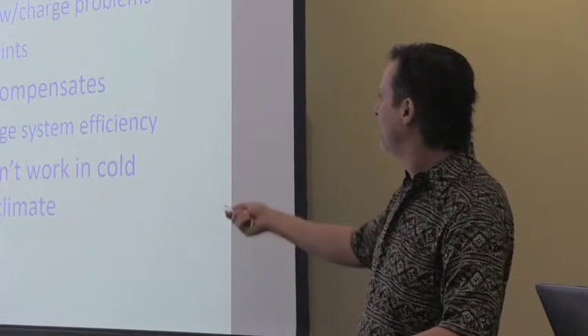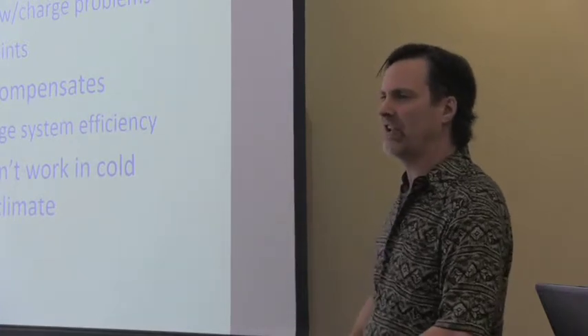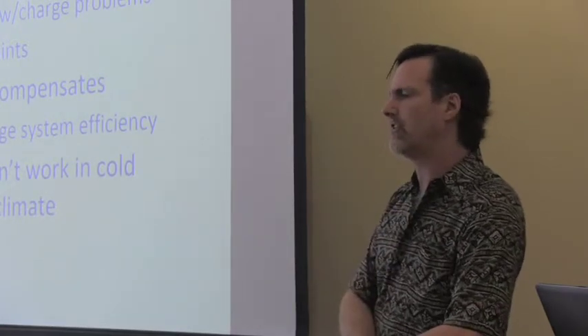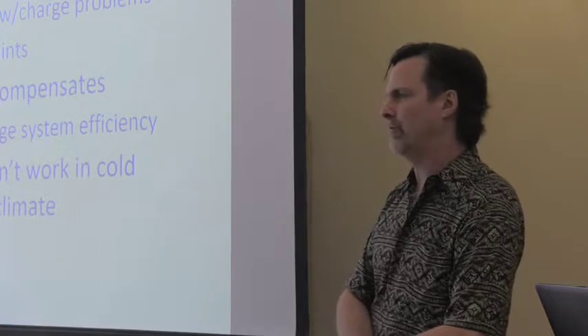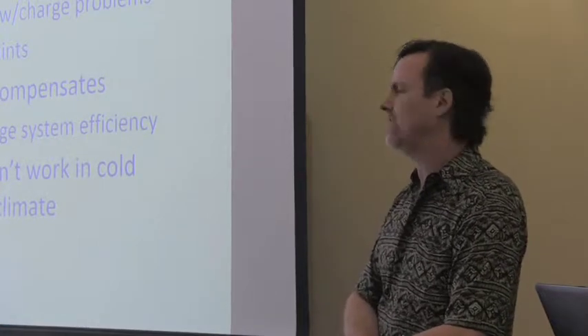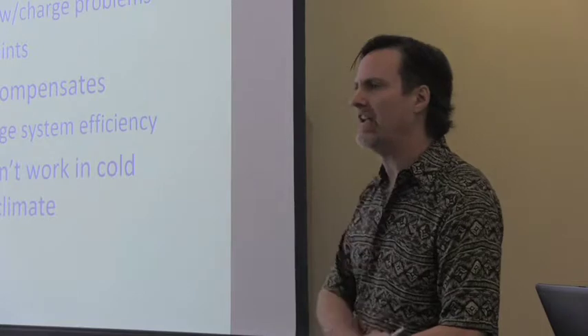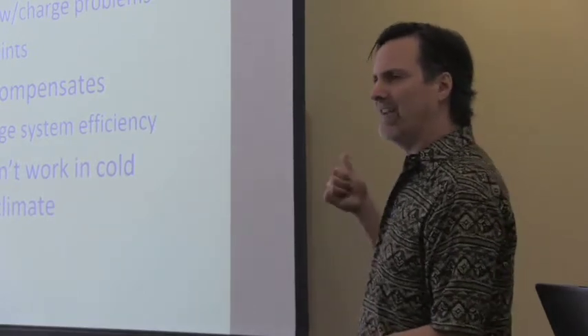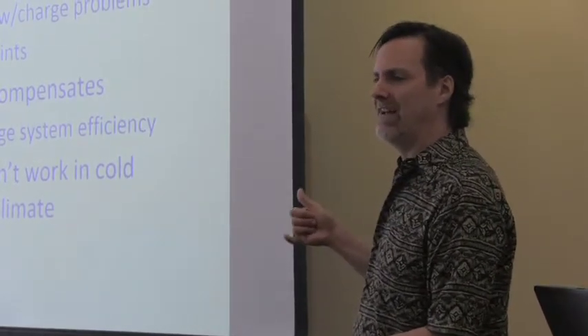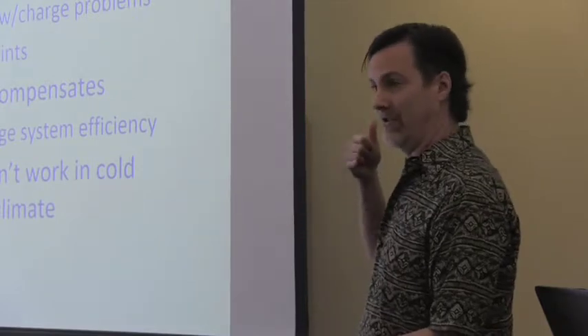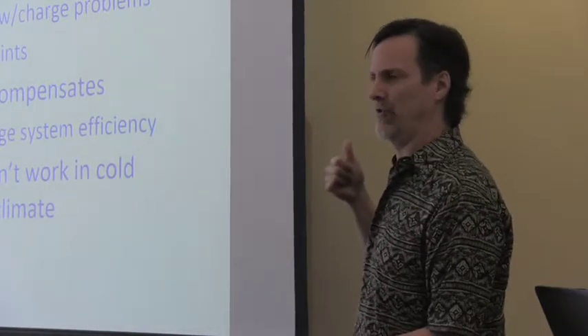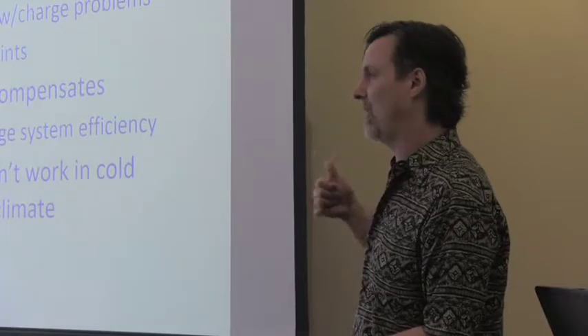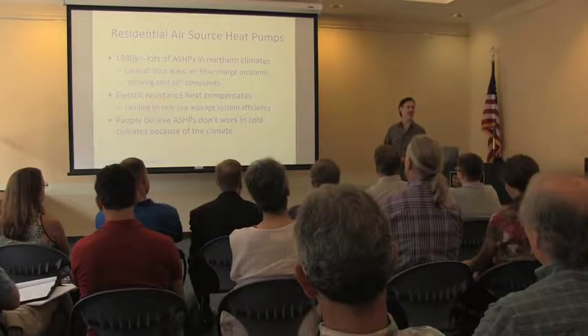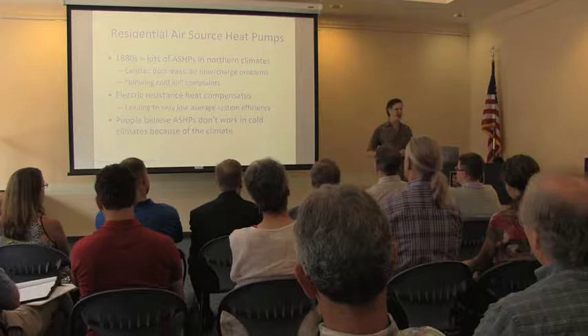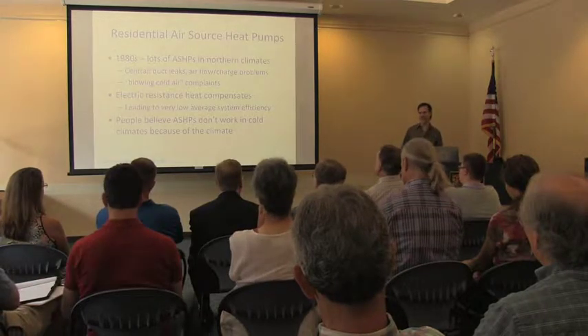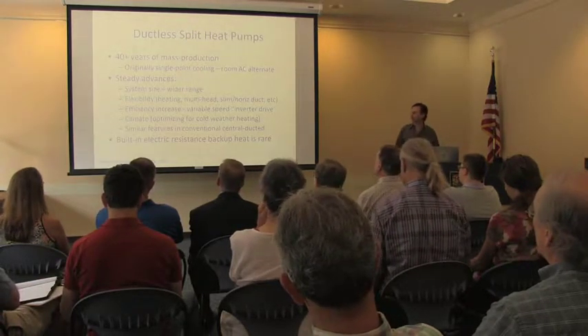It was because most of the installations, or at least a large majority of the installations, were done very, very badly, and this electric resistance heat made up the difference. So if your heating system doesn't produce enough heat, most people will call their installer and say, my house is cold, can you come out and look at the system? And maybe there was something wrong. But with that giant toaster in the ductwork, that masked the problem, and nobody knew to call their installer and say, hey, this thing isn't working the way it's supposed to.